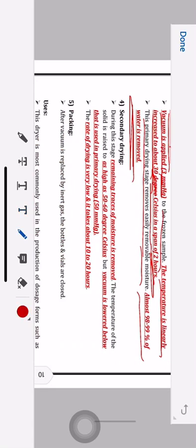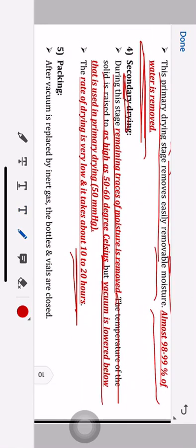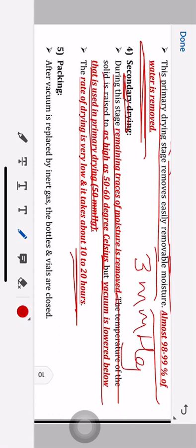Fourth step — secondary drying. After primary drying, the secondary drying removes only the remaining 1 to 2 percent of moisture, which takes about 10 to 20 hours. During this stage, the temperature of the solid is raised to as high as 50 to 60 degrees Celsius. The vacuum is lowered — in primary drying we used 3 mmHg, but in secondary drying it is 50 mmHg — so less vacuum than in primary drying.